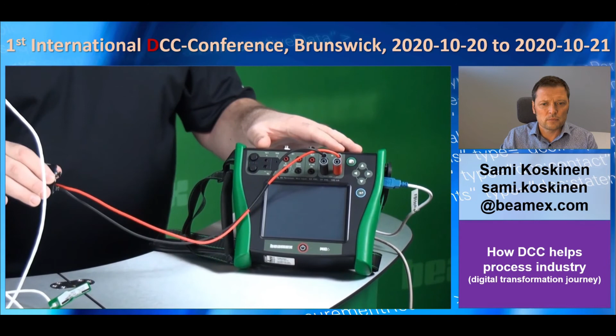If we need, we can have a more accurate sensor. In this case, we put in a high accuracy temperature reference probe, and we've got that plugged into the front of the dry block. Now, if your temperature block model doesn't include this port, you can connect this reference probe right to your MC6 here.